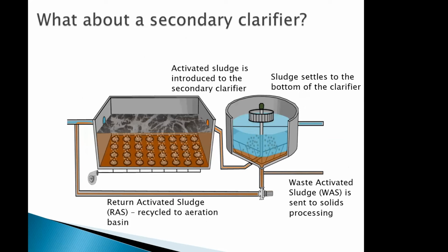Now, secondary clarifier works very similarly. The only difference is we're feeding it mixed liquor suspended solids. So we have this high concentrated bacterial soup that we just generated in the activated sludge tank. And now we need to separate the solid material from the liquid material. So the sludge is going to settle to the bottom. We'll have very low BOD, low TSS effluent overflow the top of the tank. And that'll be our clean effluent that goes on either onto your disinfection or perhaps more filtration or other advanced treatment.